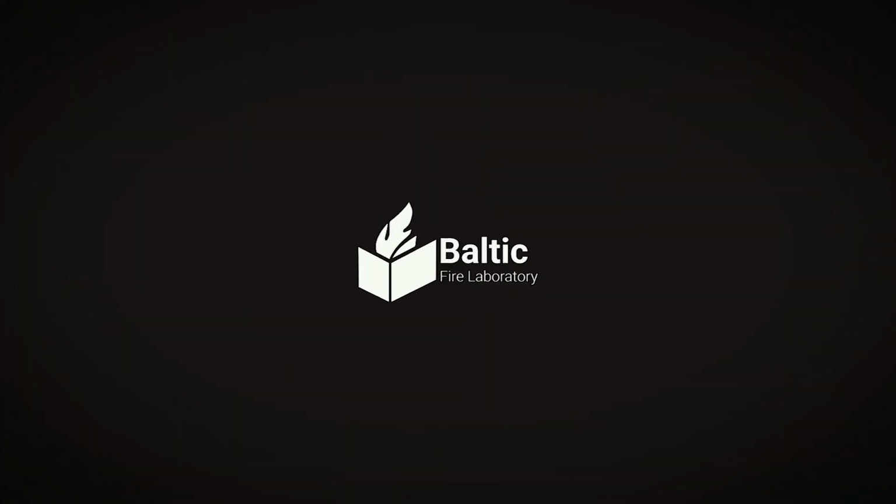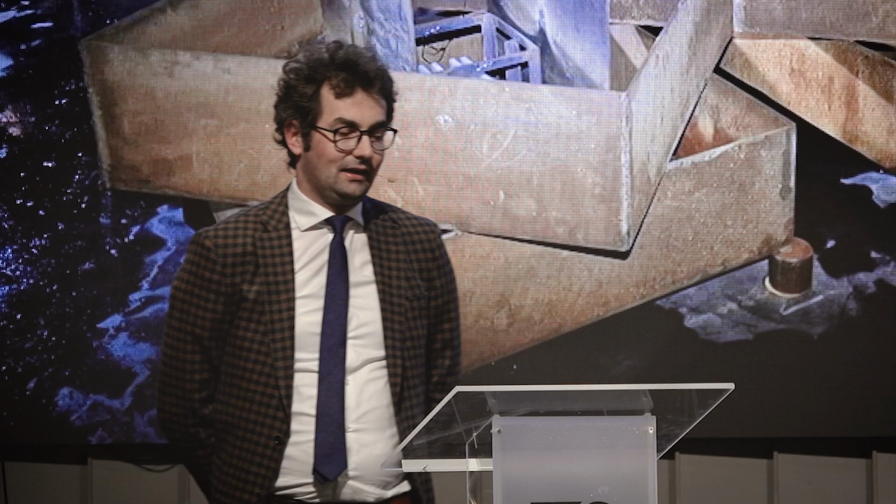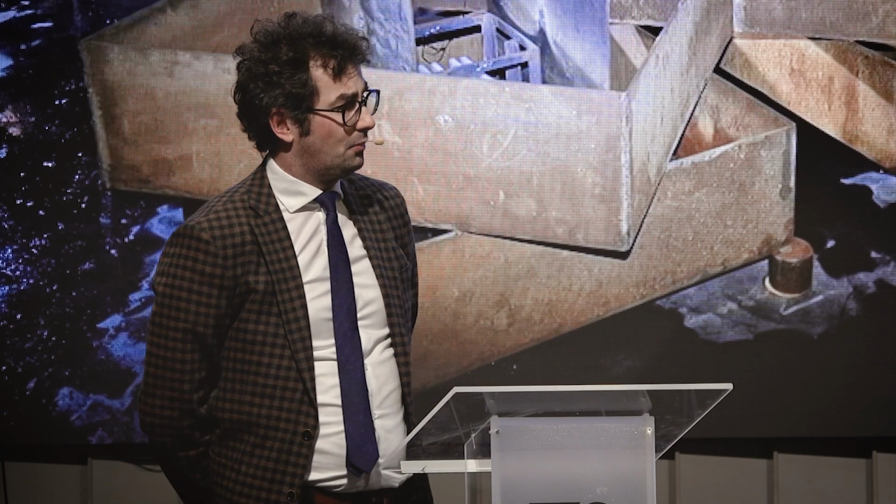But in the marketing materials you do not see this effect, because it is just a disadvantage of the system. All systems have advantages and disadvantages, and as a laboratory we need to be open with our audience and tell how this works. And this is the view after the test. You can see some rust, and I will leave the decision to you, because I do not want to be against the clean agent manufacturers, but this is our observation only. And if there is any mention of rust in the marketing materials, I don't think so.